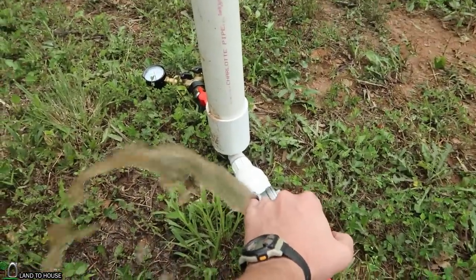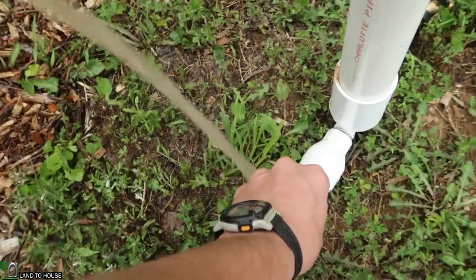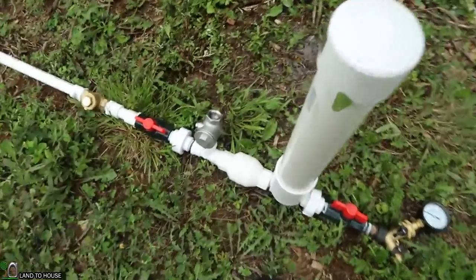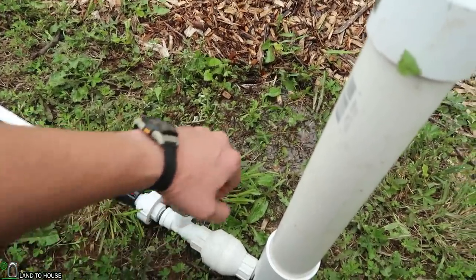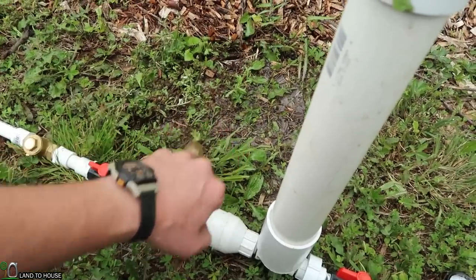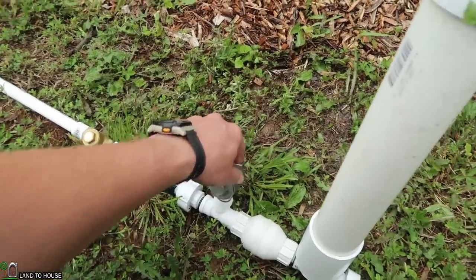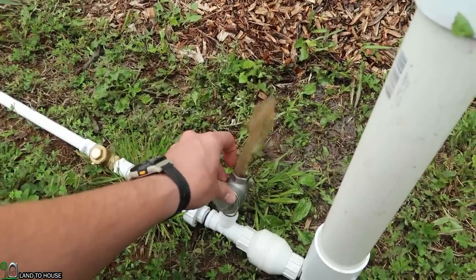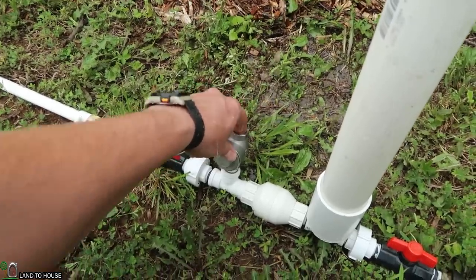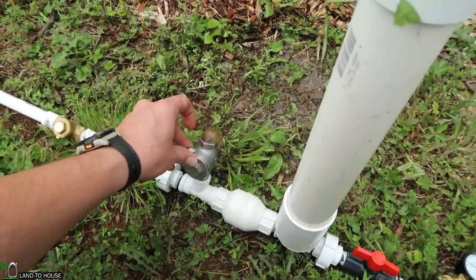Let the air out of here again. I think the air is out — let's see if this thing will prime again. So far we're not getting anything. Normally it would have started by now. I'm thinking if you add a valve here it doesn't allow the pressure wave to travel anywhere and the pump just doesn't start. Nothing's happening — it should be. Our pressure is getting close to 20 just me doing this manually, but we have no cycling.